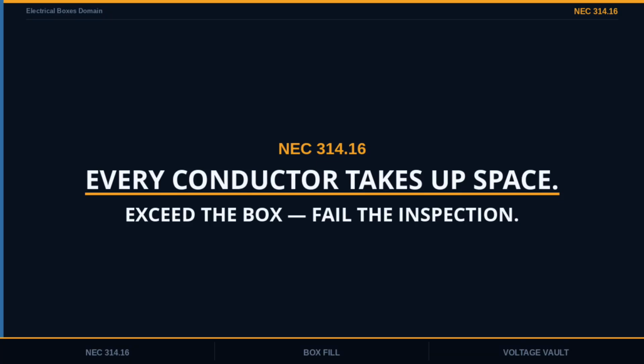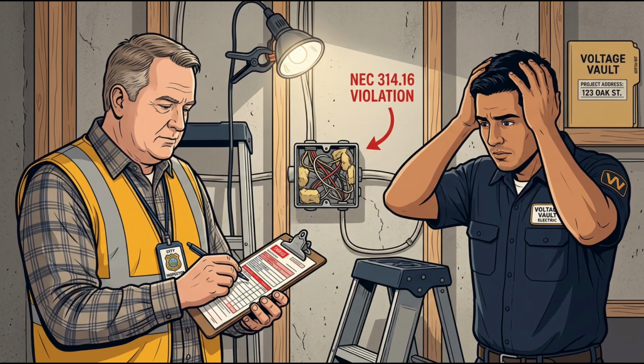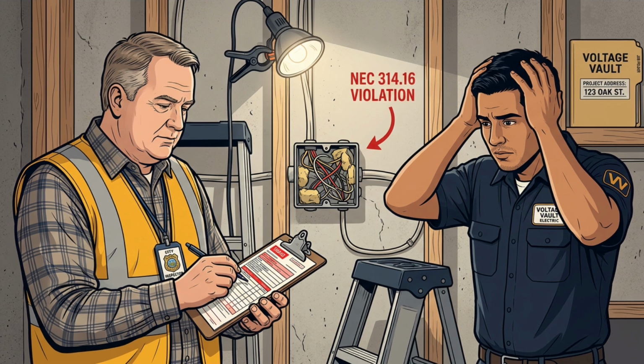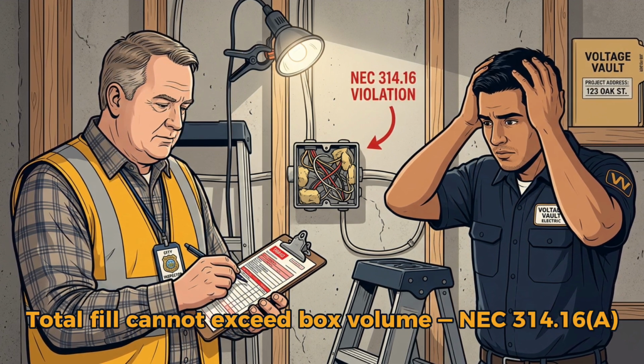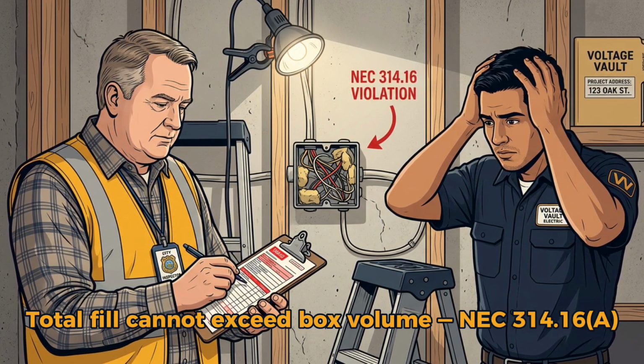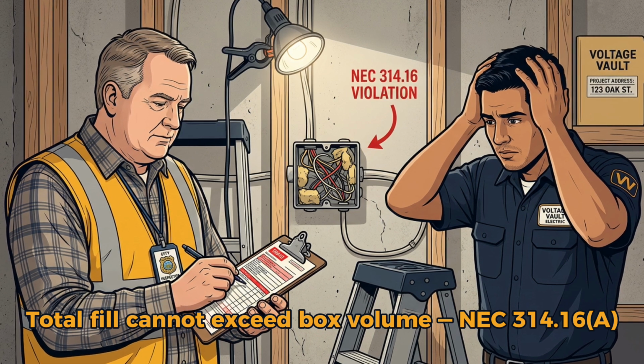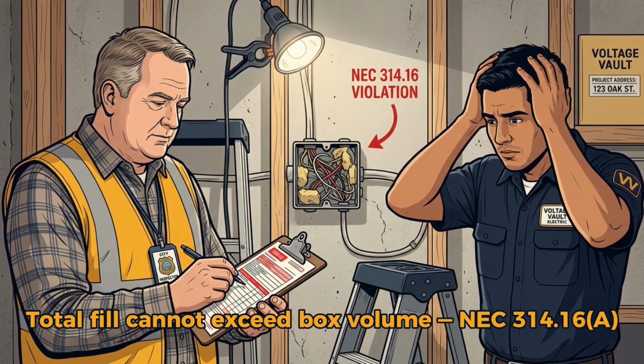NEC 314.16 requires that every box have enough cubic inch volume to hold all the conductors, devices, and fittings inside it. The code gives you a specific number for each item. Add them up. If your total exceeds the box volume, it's a violation.